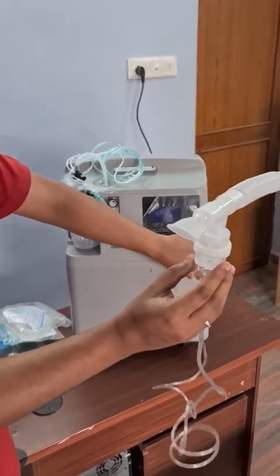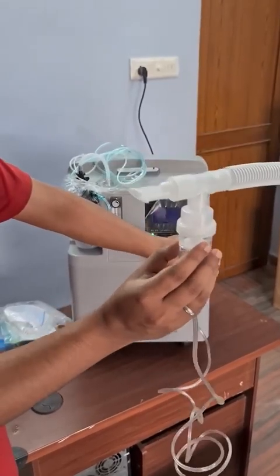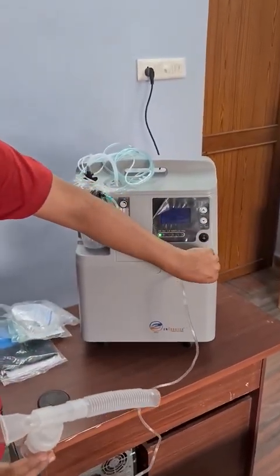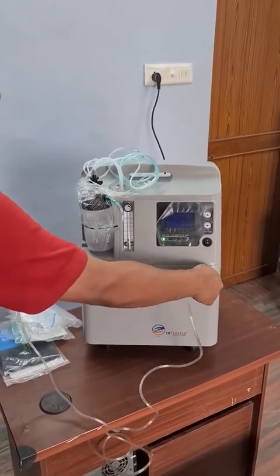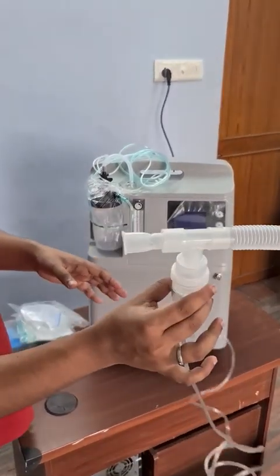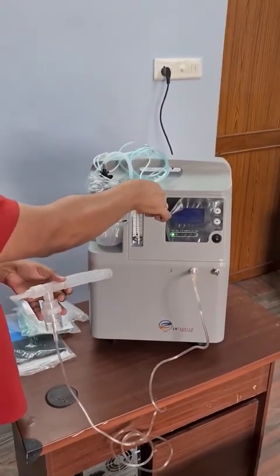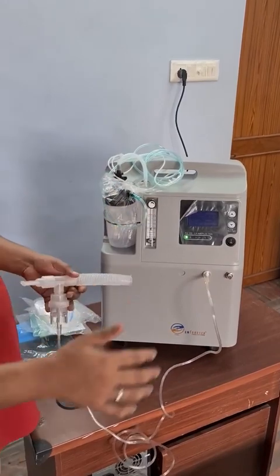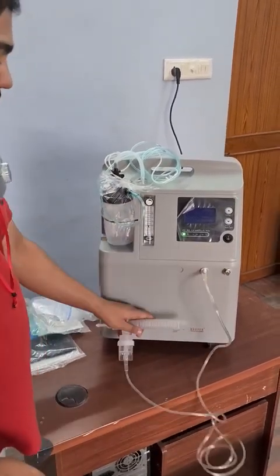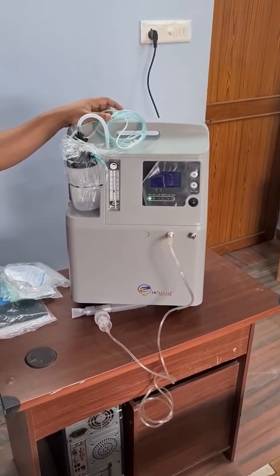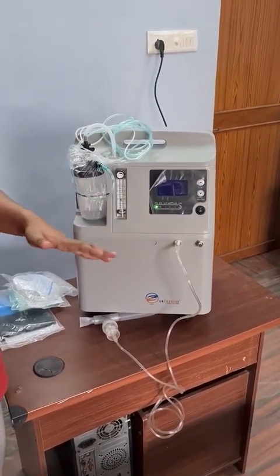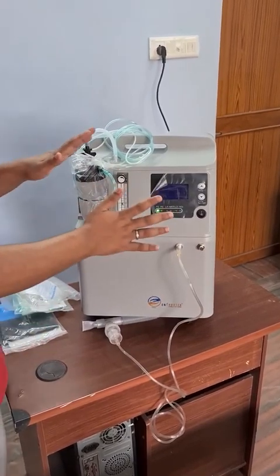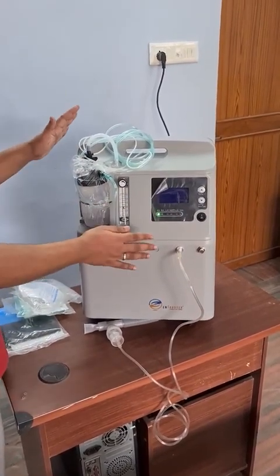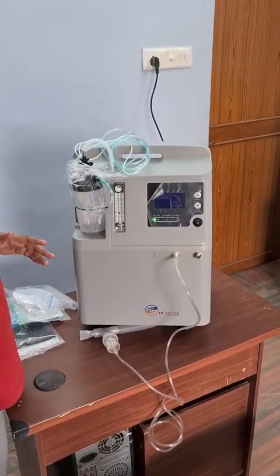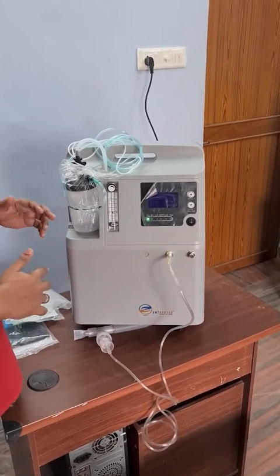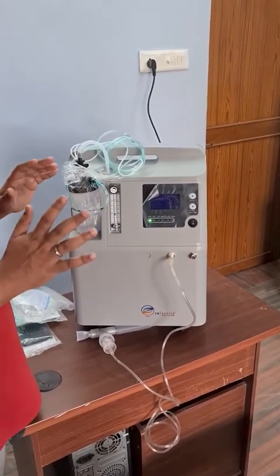This is the way to use the nebulization, and once your nebulization process is done, always make sure to rotate the knob clockwise and make sure the nebulization is 0, and then you again switch on the concentrator part so that oxygen is getting outputted. And always remember, don't keep both the ports closed. Whenever you are switching on the device, make sure that either you are using it for the oxygen concentration or you are going to use it for the nebulization part. Keeping both at 0 will cause back pressure to the compressor. So always make it a practice.